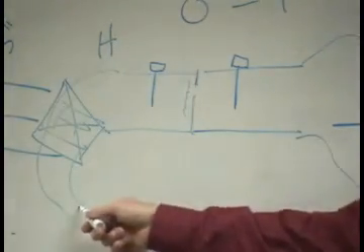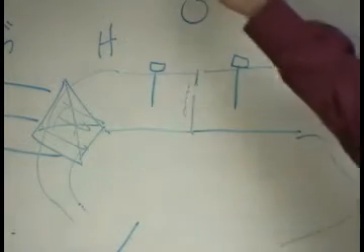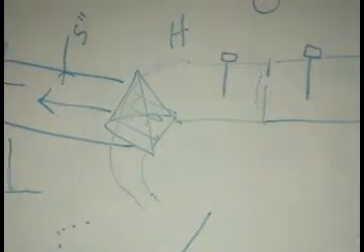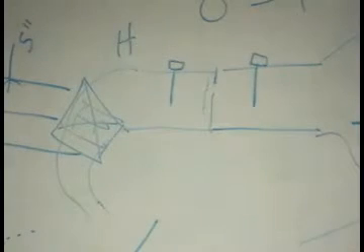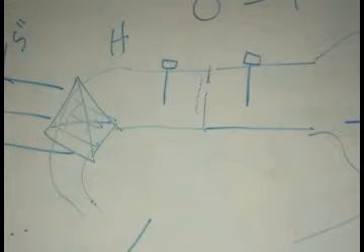And the other thing is, by the book, those tubes can't be more than 18 inches long if it's 1/4 inch. I believe it says 18 inches. And if it's longer than that, they want you to use 3/8, because if you have too long of a distance, you're trying to send 0.05 through a little tube 10 feet away, you lose a lot in your lines. So keep those lines as short as you can. They've got to be absolutely tight because you can't afford to lose anything.